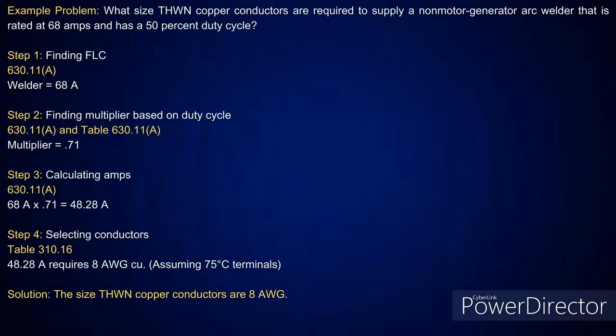All right. So in this case, I've got a welder that's 68 amps and it has a 50% duty cycle. Now, when you get to looking at the duty cycle for a non-motor, you're going to look at table 630.11(A). We already know that the welder is good for 68 amps. We gave you the information. Then I go look at the multiplier that's going to be based on the duty cycle in table 630.11(A). It's going to tell you it's at 71%. Okay. And the 71% is based on it being a 50% duty cycle. Then all I'm going to do is just calculate the 68 amps times 0.71, and that's going to give you 48.28 amps. Go to table 310.16, 75 degree C column. The next size above that is 50 amps, which requires a number 8 conductor.